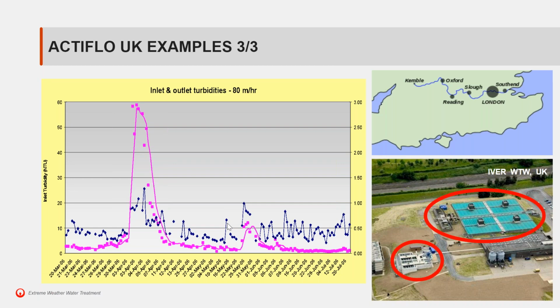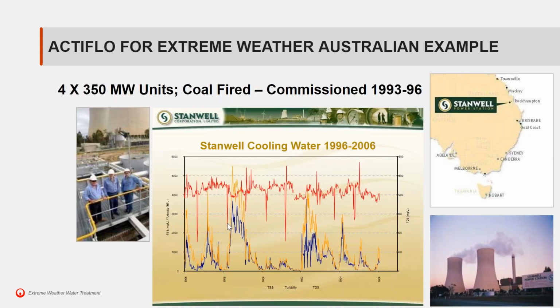An example of this sort of scenario, this time in Australia, at a power station at Stanwell. On the graph you're seeing the turbidity and total suspended solids in blue and orange, and red is the total dissolved solids. You have these very sudden changes in turbidity from the Fitzroy River, which supplies the cooling tower. Actiflo was implemented to remove these very high levels of suspended solids and get rid of the mud that was literally accumulating at the bottom of the cooling towers.